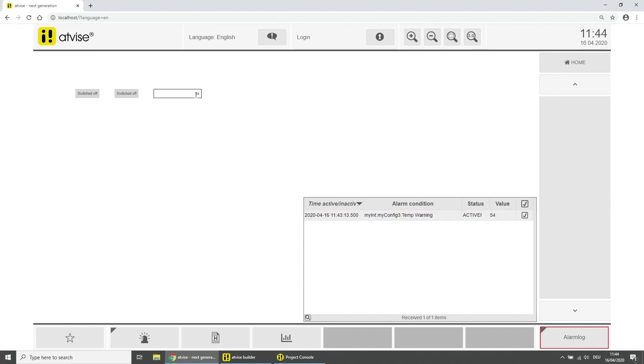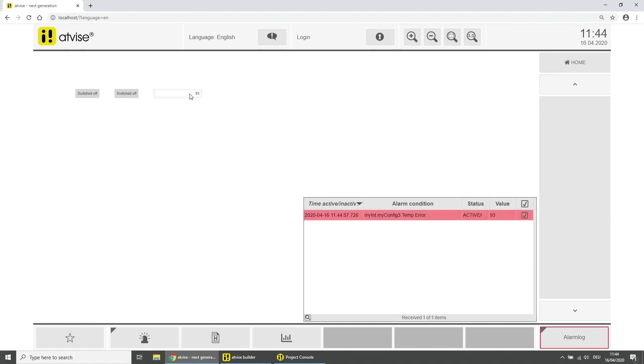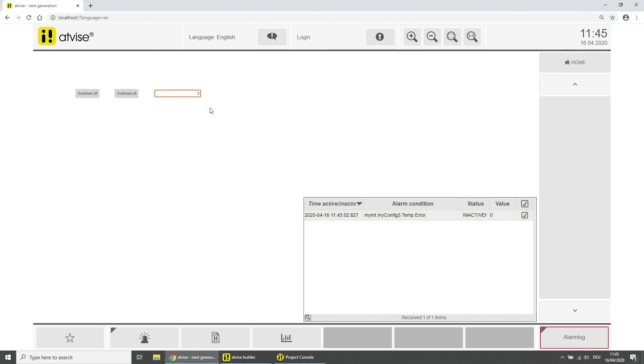Set the value of the in-out value element to a value below 50. The alarm is automatically acknowledged because of our settings in the alarm category Warning. Now set the value above 90 and then below 50. An alarm of the category Error will be triggered which has to be acknowledged manually. Acknowledge the alarm.